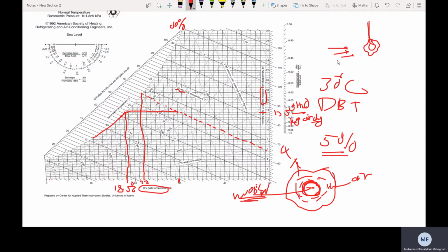And taking some moisture from this wet cloth, what is the temperature of the air after it passes here? So it is a kind of a measure of the humidity of air, because we cannot measure humidity by conventional devices. Now, yeah, we can measure it, we have many ways, but in the past, if you wanted to measure the temperature of the air, you had the thermometer. But how can you measure the humidity of the air? There is nothing to measure humidity directly. So what happens is that if your air is not 100% humid, then it will take some of the moisture here, and you'll have a temperature reading there. This temperature reading will tell you how humid your air is.